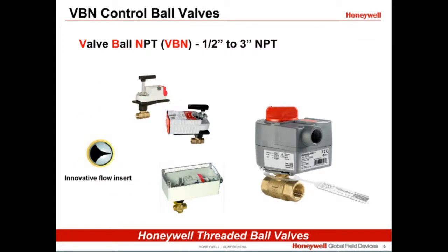Honeywell offers a broad portfolio of characterized ball valves for HVAC applications. VBN series stands for Valve Ball NPT. Threaded VBN valves are available from 1/2 inch up to 3 inches in two-way valves and up to 2.5 inches with three-way ports. They can be ordered as valve body only or as assemblies with an electric actuator. They are also used with direct couple actuators like the MN6105 or MN7105. But they all can be used with the new, easy-to-use MVN actuator on sizes up to 1 1/4 inches.